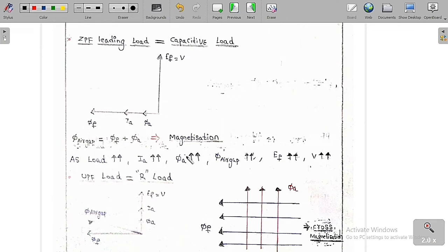This is called the field flux, and this is the EMF induced in the stator coils, which is nearly equal to the terminal voltage. As it's a leading load, the current IA is going to lead the EF. IA and phi a, since IA produces the armature flux, are always in phase with respect to each other. So we can say phi f is in phase with phi a.